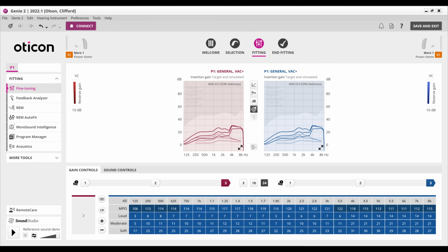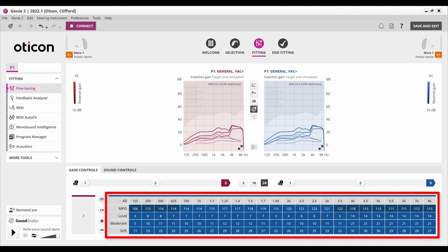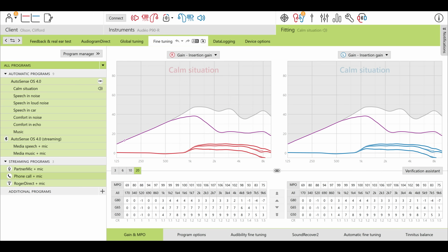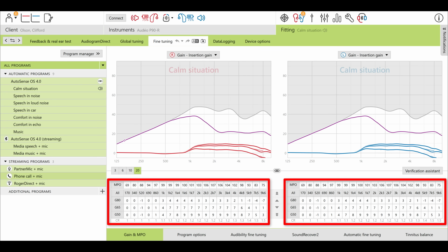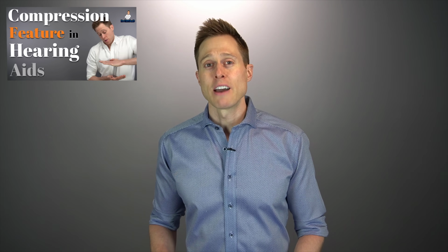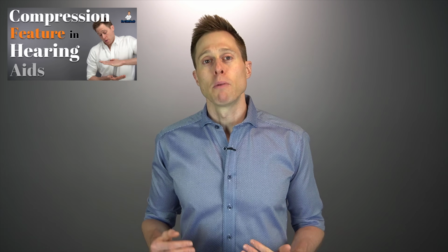Both Phonak and Oticon custom ear molds improve the programmability of their devices, which happens to be the next category that I'm looking at. As far as overall programmability goes, the Oticon More hearing aids have 24 different adjustment bands that their frequency range is broken into, and the Phonak Paradise hearing aids have 20 different frequency bands. This means that the Oticon More devices are slightly more customizable than the Phonak devices when it comes to a frequency standpoint. However, from a compression standpoint, I find that the Phonak hearing aids are much more precise when making amplification changes for loud and soft level sounds.